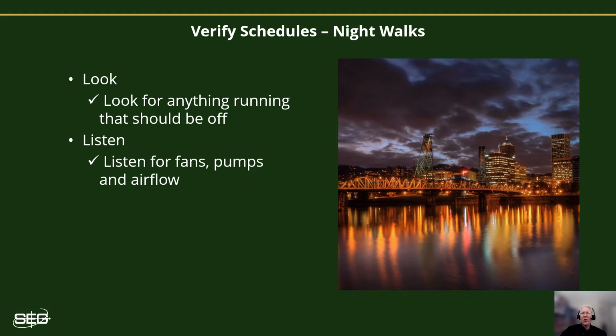Listen. Can you hear the rumbling of equipment or the airflow whistling through ductwork? Can you feel any air currents flowing as you move about the building? That could indicate fan systems running or perhaps a leaky building envelope. Realize also that night low limit and night high limit can bring systems on for short periods of time overnight. So when you find HVAC running, make a note of the time, as well as the building temperature and the outside air temperature at the time. These could be helpful to know when investigating further. You can compare this to trends in your BAS and determine if they were actually supposed to be on.